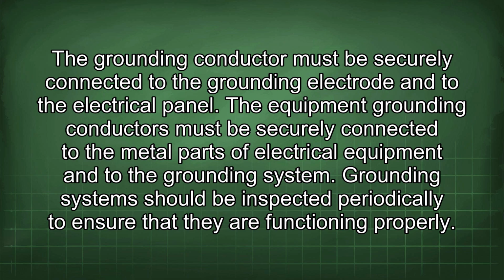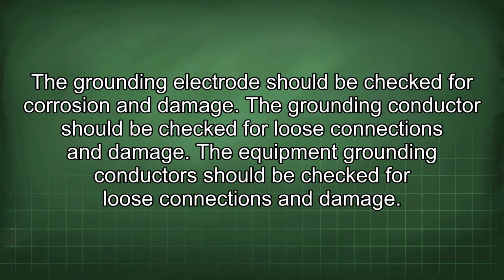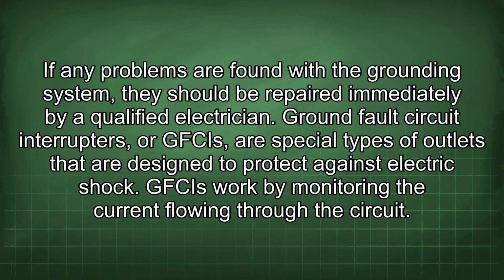Grounding systems should be inspected periodically to ensure that they are functioning properly. The grounding electrode should be checked for corrosion and damage. The grounding conductor should be checked for loose connections and damage. The equipment grounding conductors should be checked for loose connections and damage. If any problems are found with the grounding system, they should be repaired immediately by a qualified electrician.